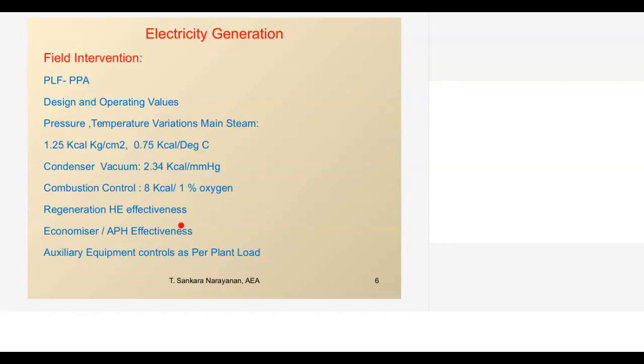Because many a time we see APH leakages, but it is not a small industry where I can stop the plant and repair the APH. So APH correction itself will take 1 year or 1.5 years. When the plant goes for annual maintenance, that time one can do certain improvements. Otherwise, we will be able to identify why certain heat rate is increasing. So this is one of the things we have to think about.